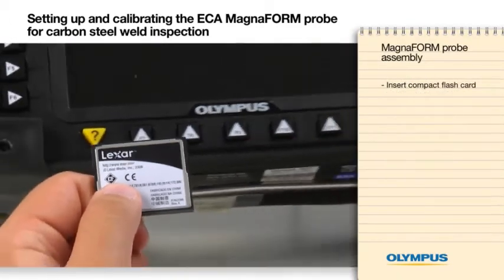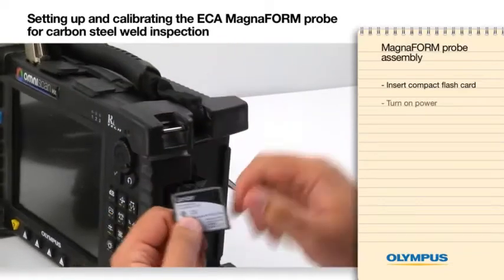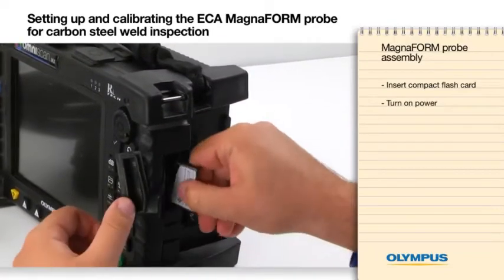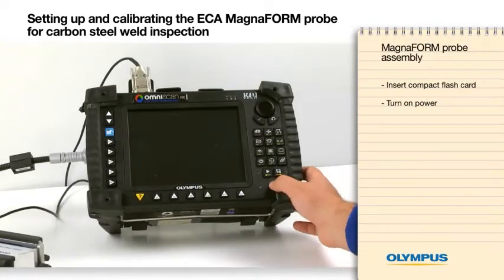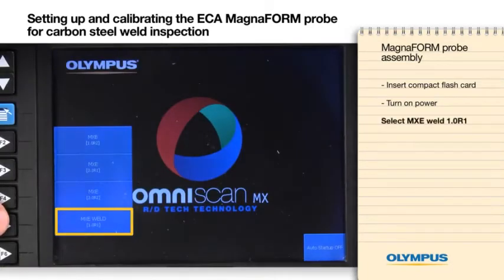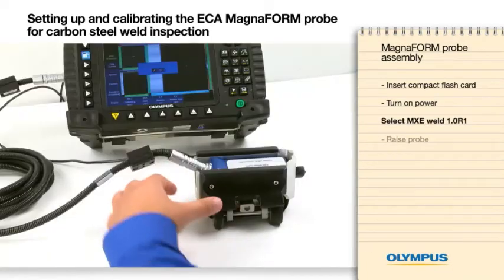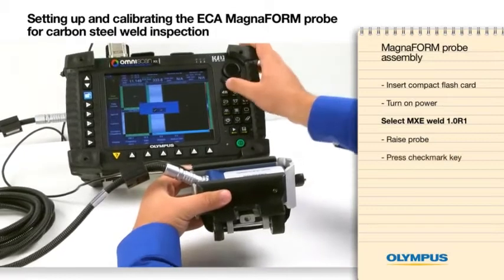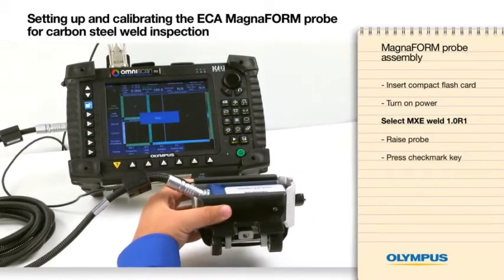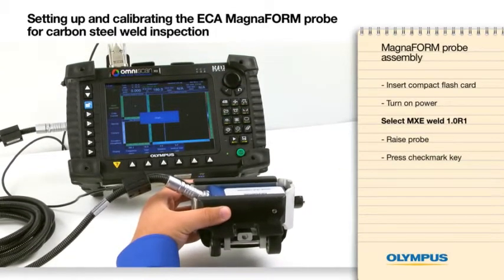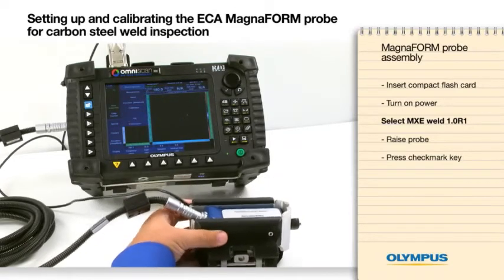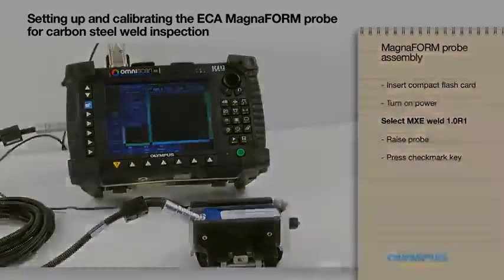Insert the compact flash card into the OmniScan MX and power on the instrument. Select MXE Weld 1.0 R1, raise the probe and press the checkmark key. We are now ready to begin calibrations.